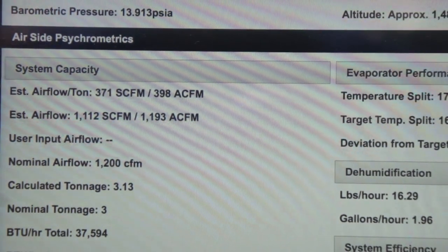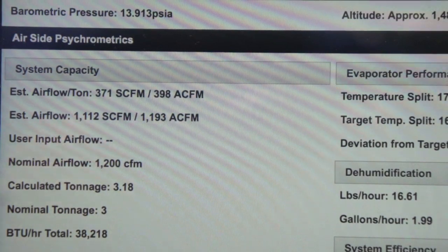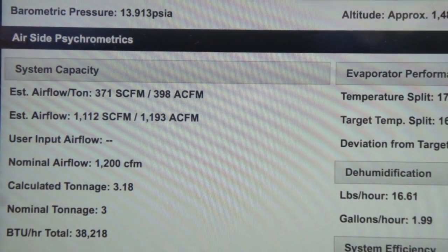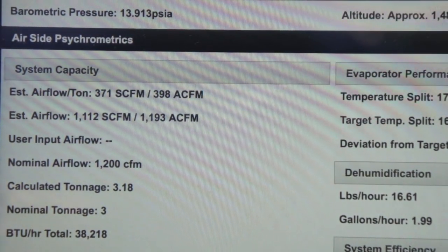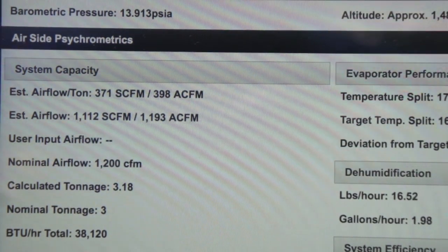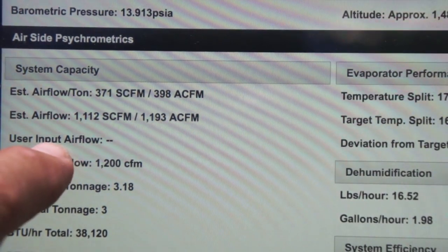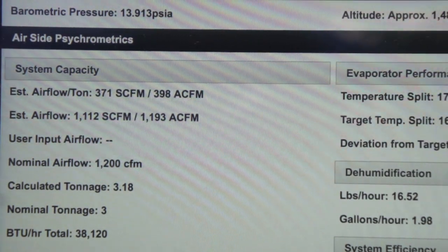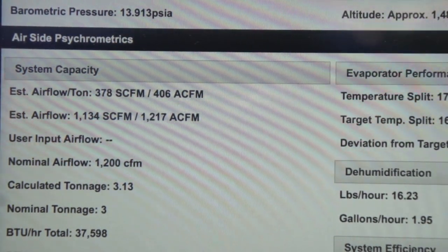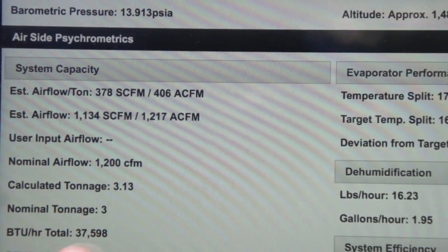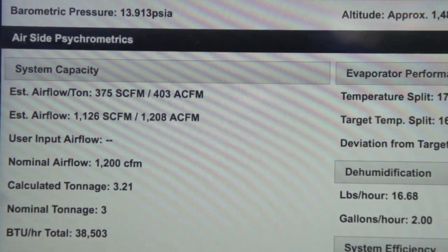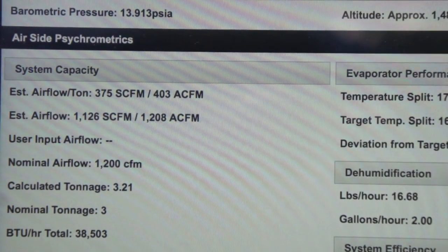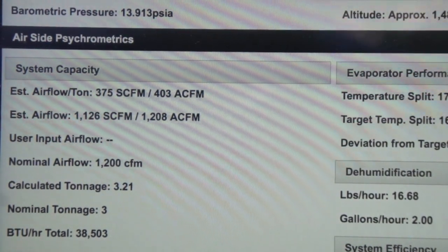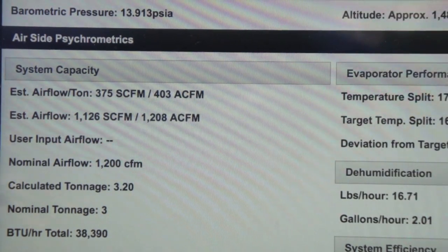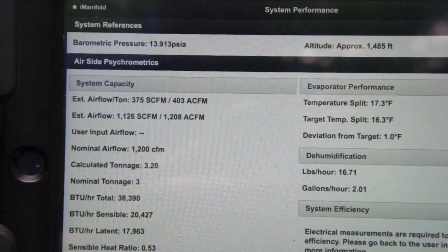And you can see that it's an estimated airflow. It's calculating it off the coil performance and off the supply air, wet bulb and dry bulb, and return air, wet bulb and dry bulb. And you can see that again, there's no user input here, that's blank. So we're actually calculating the airflow in real time. So this is a very, very handy feature, because we're also calculating our tonnage, our nominal tons, our BTU sensible and latent, bypass factor, everything off the 2 wireless probes. So literally in seconds, we're up and running and doing all the calculations for the air conditioning performance.